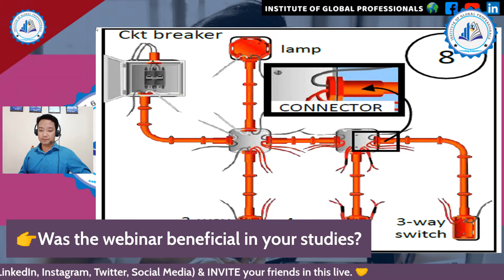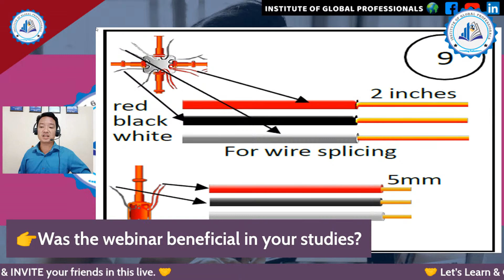And number 9, prepare the conductor for termination. Strip off at least 5 millimeters of insulation for terminals and at least 2 inches of insulation for wire splicing. Here is the example. For wire splicing, take note that wire splicing should be done in junction boxes, not in utility boxes. So 2 inches is considered for wire splicing, either for red, black, or white colored wires. While for terminals, or the terminating of the wires to the fixtures of switches, you should strip at least 5 millimeters of the wire for you to insert in the different terminals of the switch. So that is how step 9 should be done for wire splicing and for the terminals.